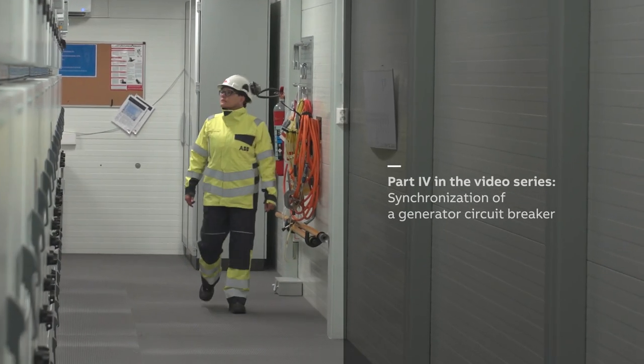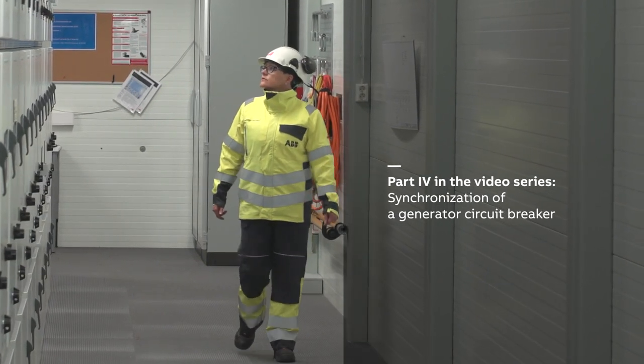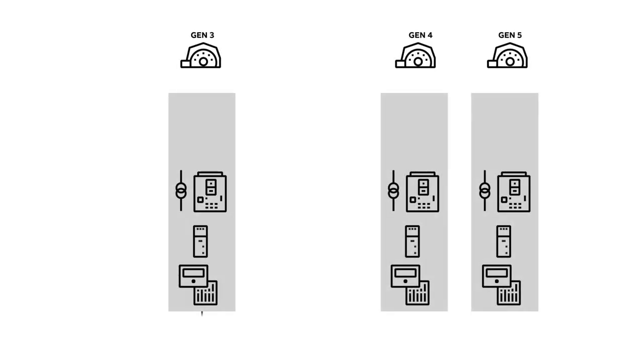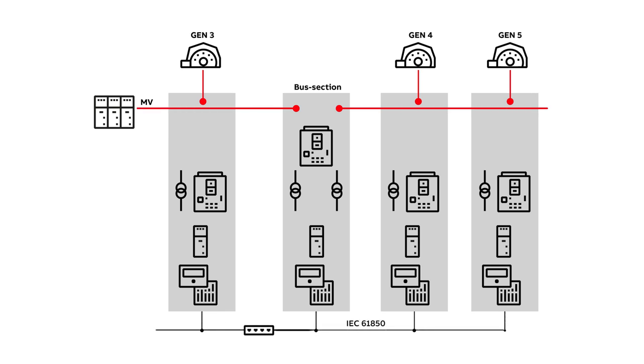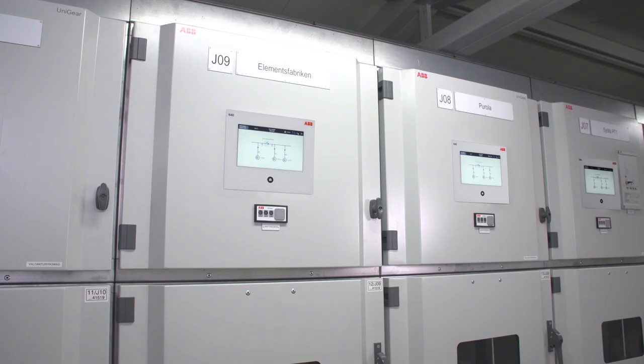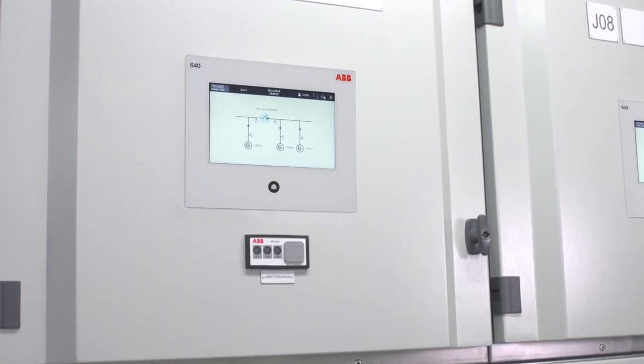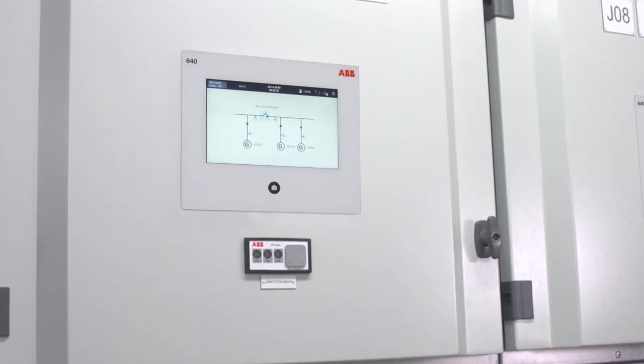To get more information, please take a look at our REC640 How-To Video Series Part 4, Synchronization of a Generator Circuit Breaker. Our auto-synchronization solution can manage large networks with several generator circuit breakers and non-generator circuit breakers. The solution automatically keeps track of the actual switching status of different primary switching devices, and depending on the selected breaker for synchronization, it can always offer the correct control view. Our solution automatically connects the necessary voltage measurement signals, generator controls, and modes for the synchronizer. No additional panels or hard wiring are necessary.